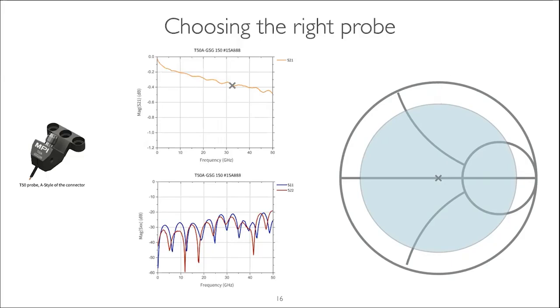The next important thing that a lot of people take for granted is the return loss. So you see here the center point of this tuning range is at 50 ohms, okay? But now depending on what frequency, if you look at the lower plot, that's the return loss of the probe. You can see here that this probe is really good across the entire frequency range, below minus 20 dB, but 20 dB is still 0.1 gamma. So at certain frequencies, let's say we look at a specific frequency here, like around 33 gigahertz, you can see that we're at minus 20 dB.